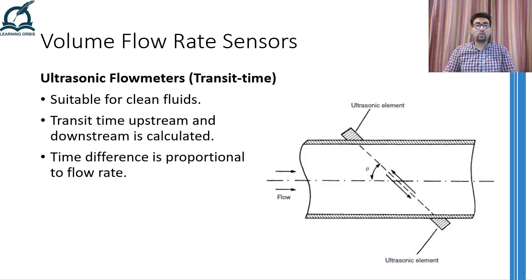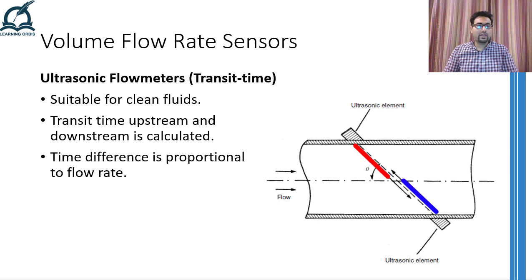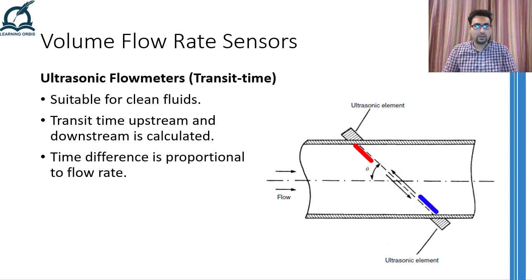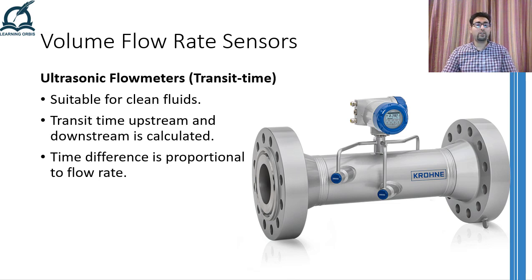The other type of ultrasonic flow meters, called transit time flow meters, are perfect for measuring the flow rate of clean, smooth-flowing fluids. In this case, two ultrasonic transceiver pairs are used. The transmitter in both pairs transmits ultrasonic waves at an angle through the fluid moving in the pipe, whereas the receiver receives the wave transmitted by the transmitter of the other transceiver pair, as shown in the schematic. The ultrasonic wave traveling downstream will take less time to travel from transmitter to receiver compared to the wave traveling upstream. This time difference is directly proportional to the flow rate, and multiplying by the cross-sectional area of the pipe gives us the volume flow rate.